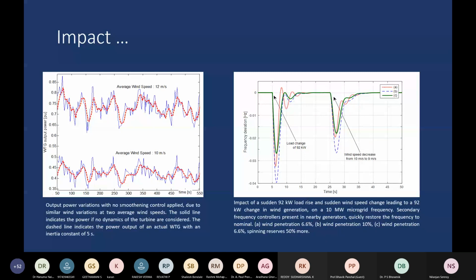And if the wind penetration is low and the spinning reserves are also present, which is curve C. Spinning reserve means that you have some other flexible resource that I was just talking about. That flexible resource immediately steps in to compensate for the change in the wind generation. So if such a situation occurs, then the frequency change is further mitigated, as curve C shows on the right.